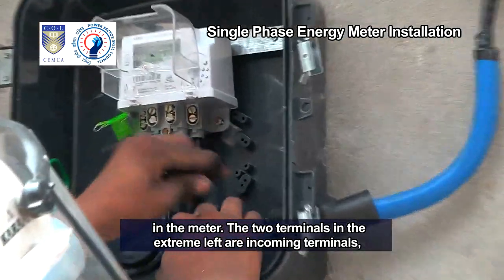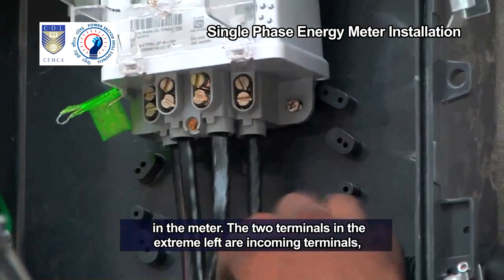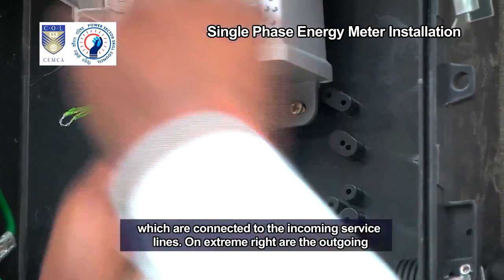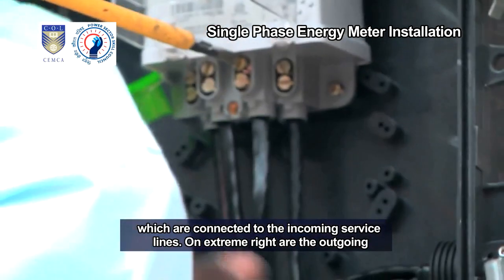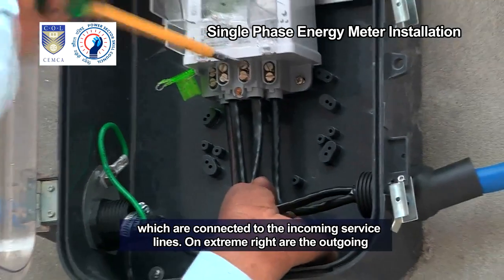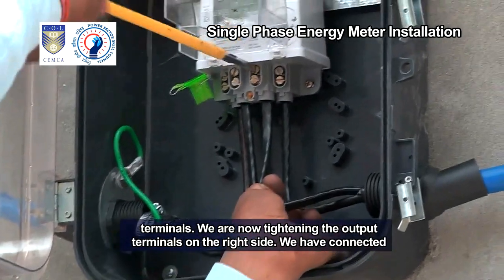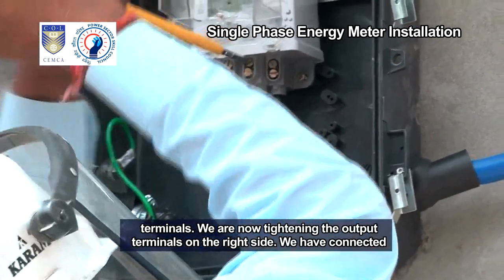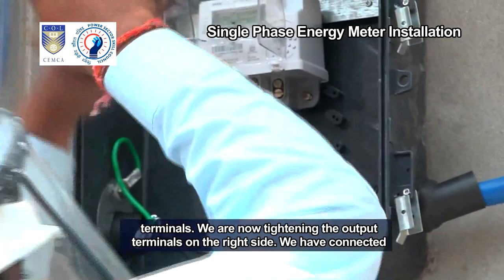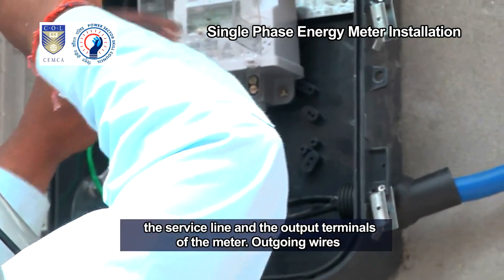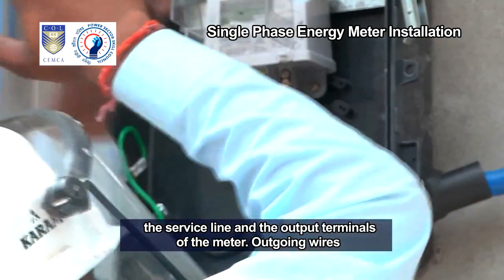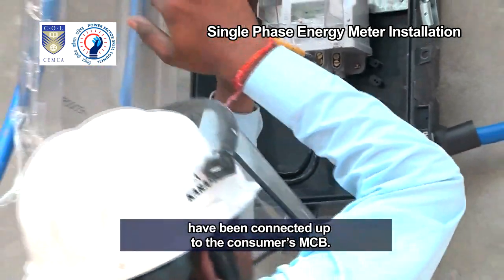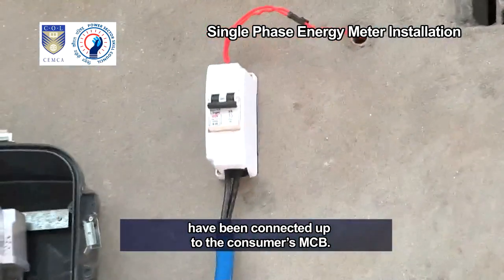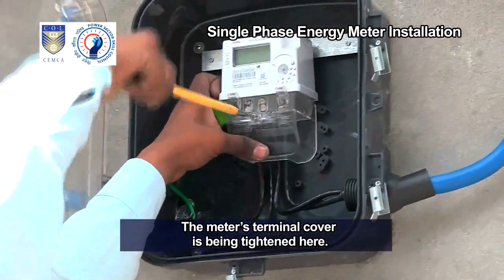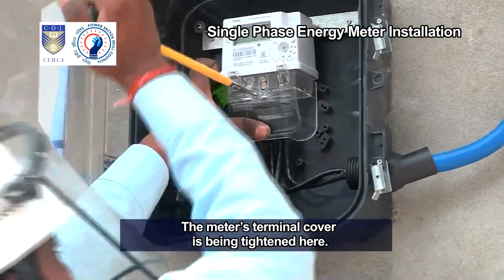The 2 terminals in the extreme left are incoming terminals, which are connected to the incoming service lines. On extreme right are the outgoing terminals. We are now tightening the output terminals on the right side. We have connected the service line and the output terminals of the meter. Outgoing wires have been connected up to the consumer's MCB. The meter's terminal cover is being tightened here.